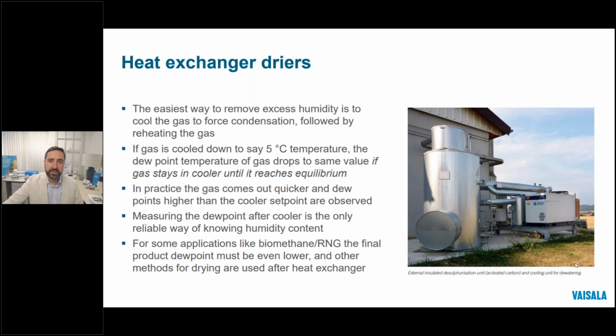And higher than intended moisture content can cause a variety of downstream issues. Alternatively, overcorrection or overdrying can waste energy by cooling the gas too much and dropping the dew point below target, which can also create some issues beyond energy waste. Next, please.